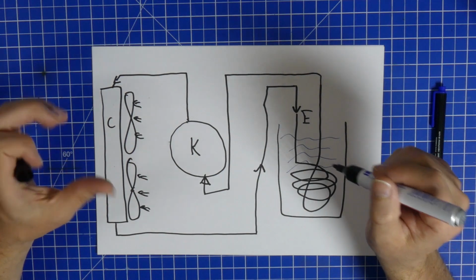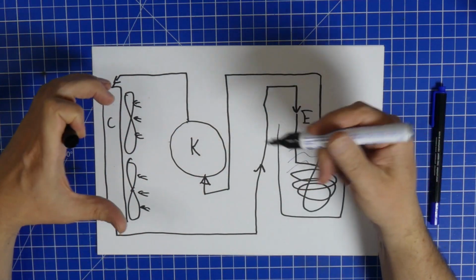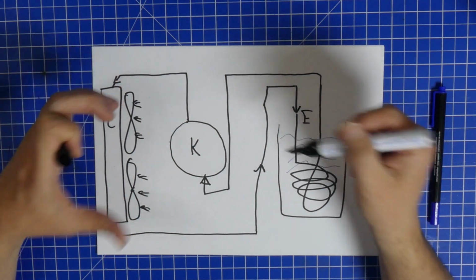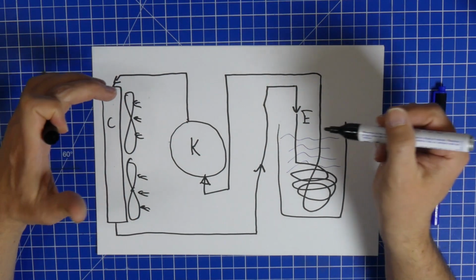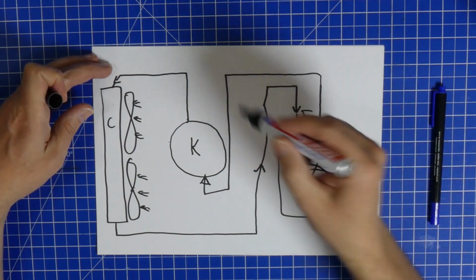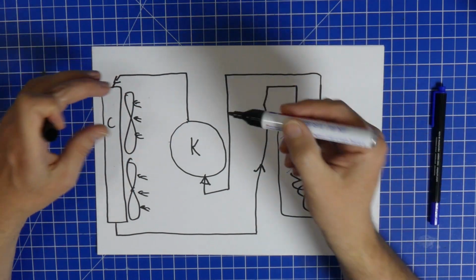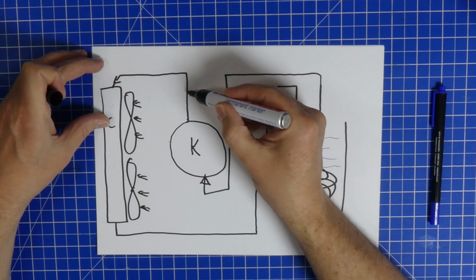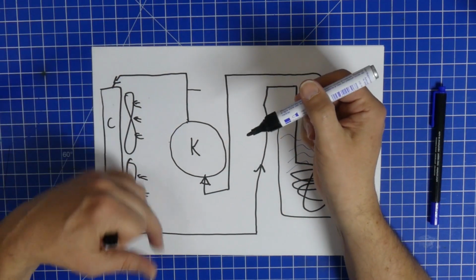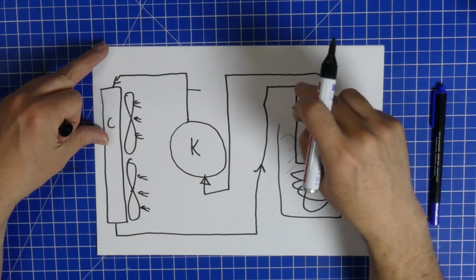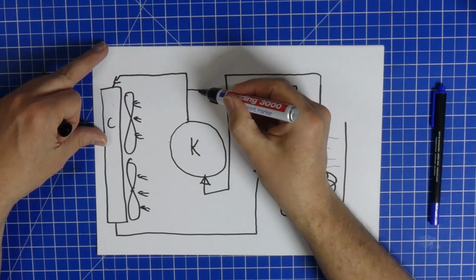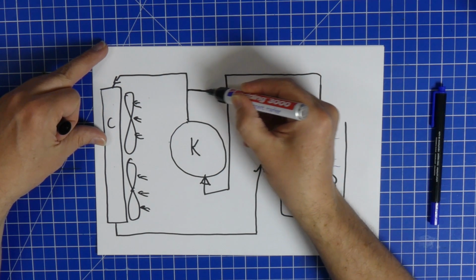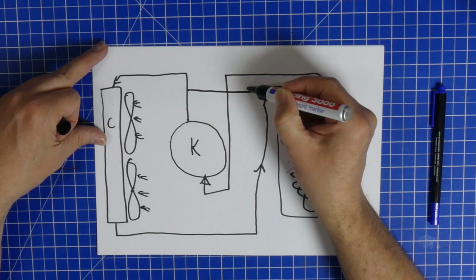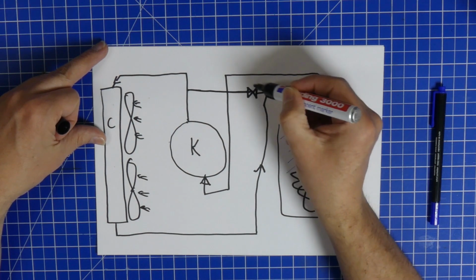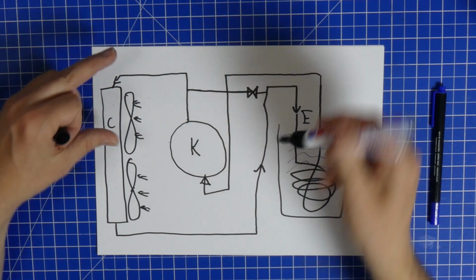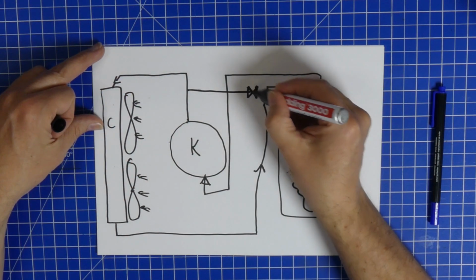Now, this setup inside the CW-5000 has something extra, and that something is called a bypass valve. And the bypass valve goes from the hot side, the pressure side of the compressor, right to the start of the evaporator, so right here. And there is a mechanical switch that can be operated by a magnetic solenoid, and this will turn this on or off.